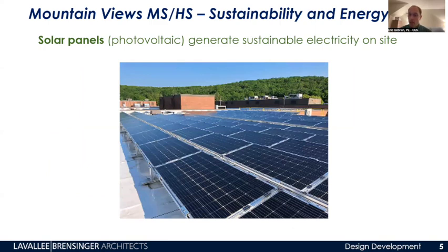There's a metric called EUI, energy use intensity—think of it like a miles per gallon rating for your car, except unlike a car, the lower the number, the better for a building. EUI is the energy use of a building over a calendar year divided by square footage, which lets you compare energy use between, say, a larger high school and a smaller one. With everything we've discussed for an efficient building design, we're looking to get the total EUI of the building to around 25, measured in KBTUs per square foot per year.